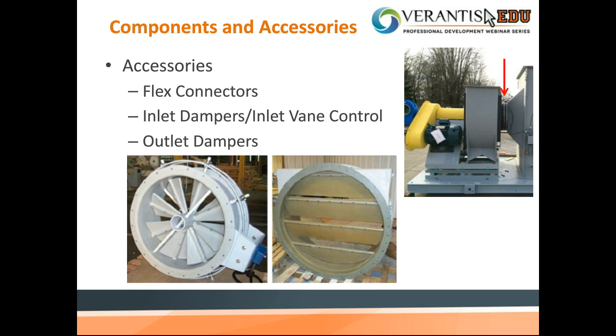For the dampers, there's a bunch of different arrangements. It can be everything from an actuated damper to a quadrant locking damper. The key is just to make sure they're open and you don't operate the fan with them closed. Otherwise, you have a significant heating issue that occurs within the housing.